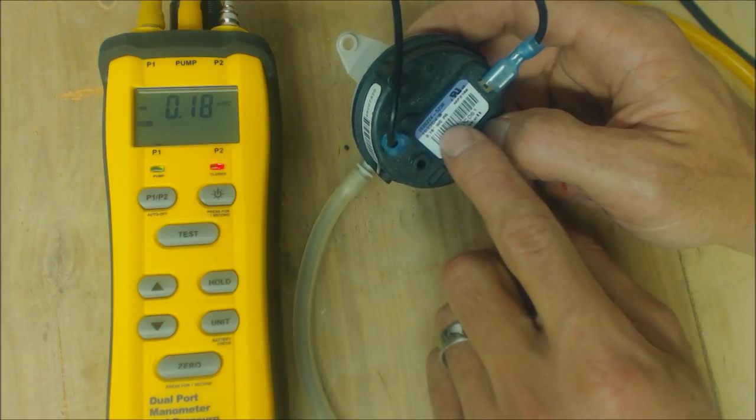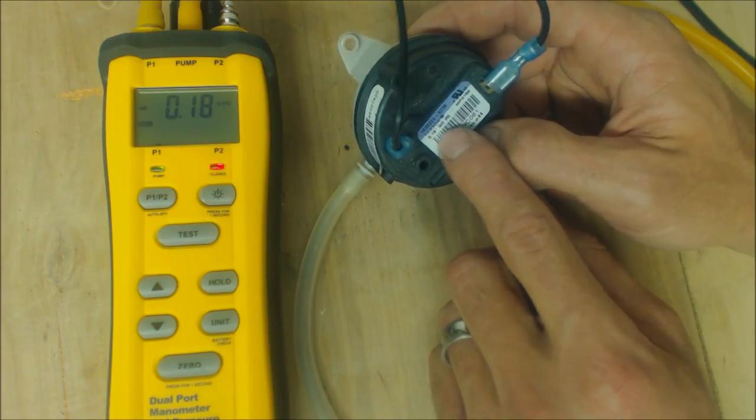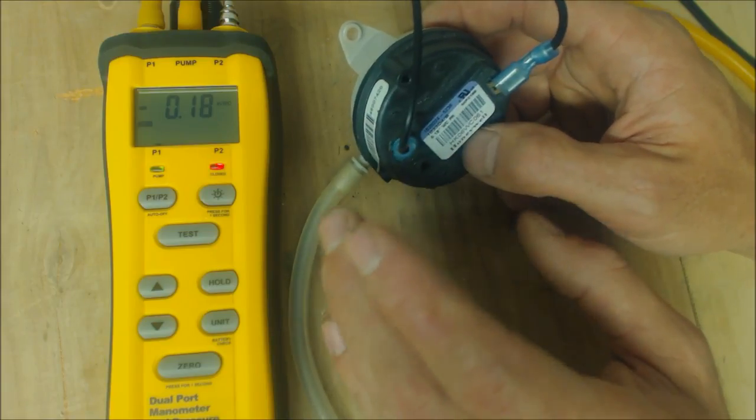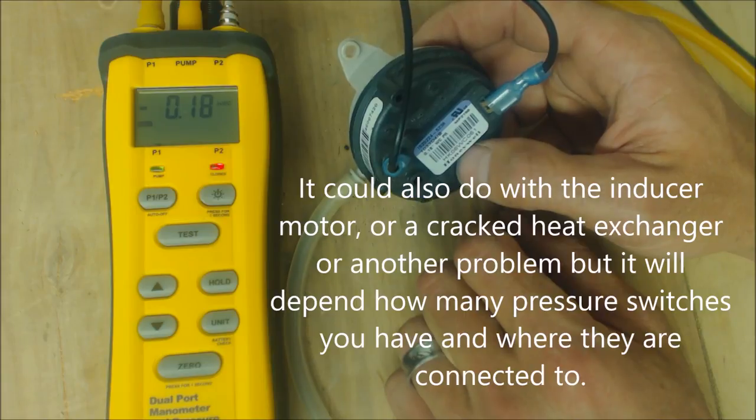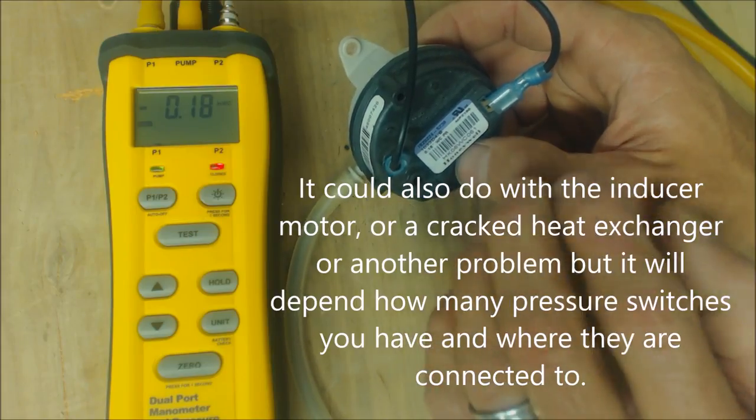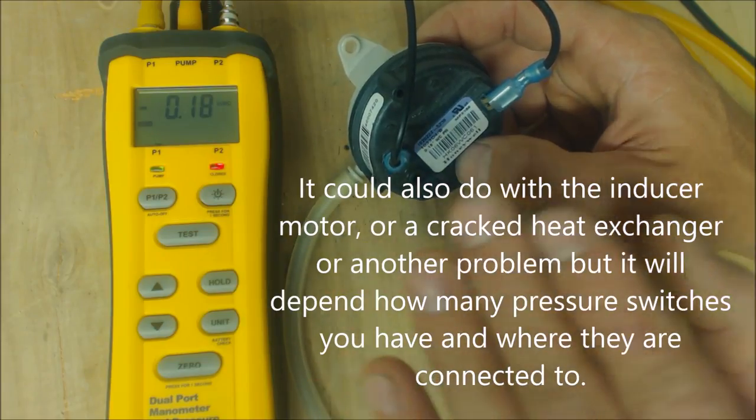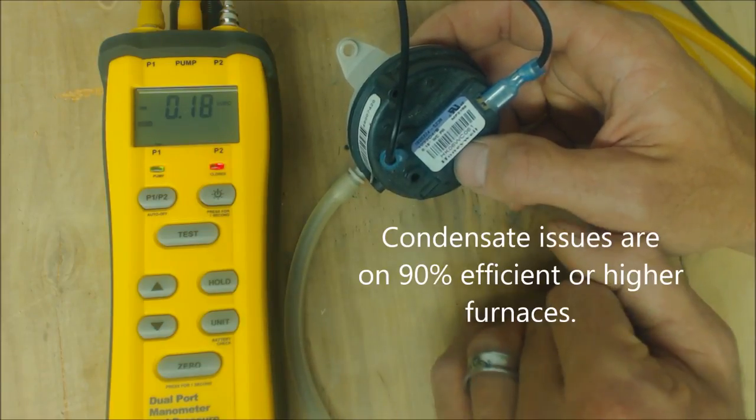It can tell you that the pressure switch is not the problem. Typically intermittent issues with furnace pressure switches have something to do with water, the condensate from the furnace, or maybe the vent pipe is not pitched correctly and there's water filling up in the exhaust pipe.